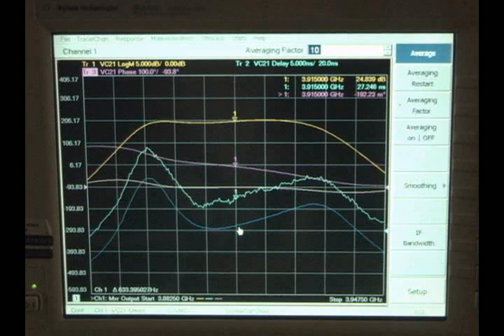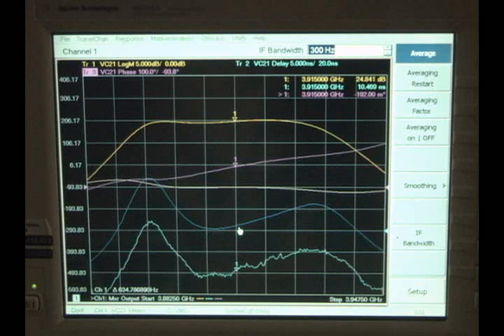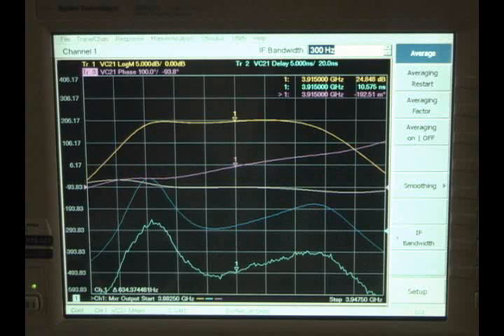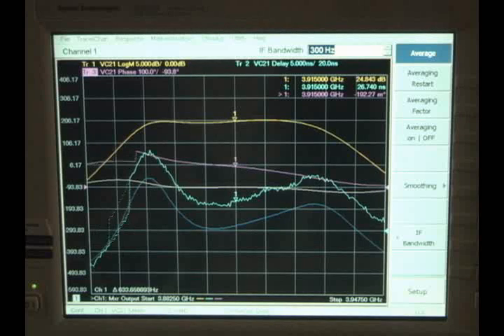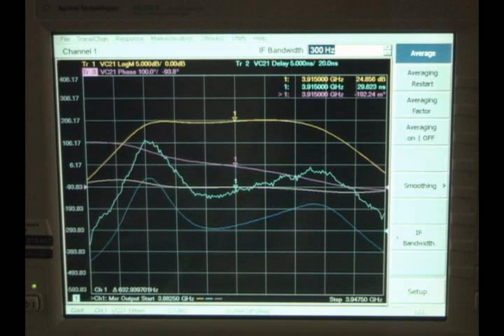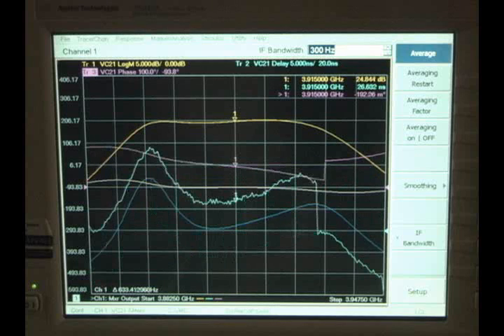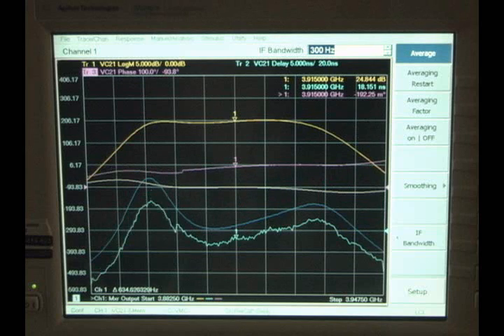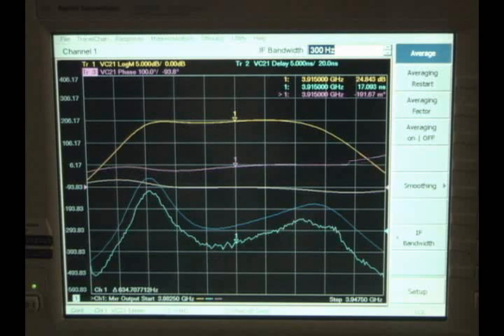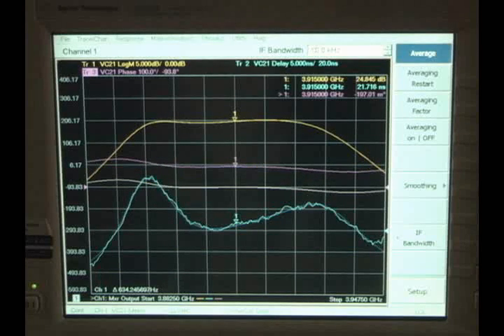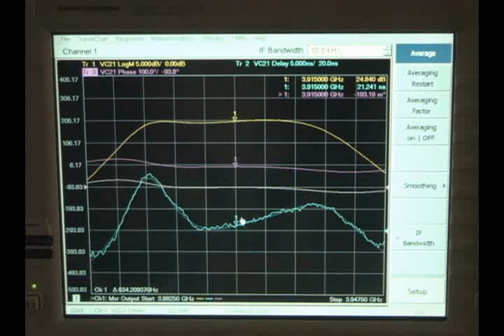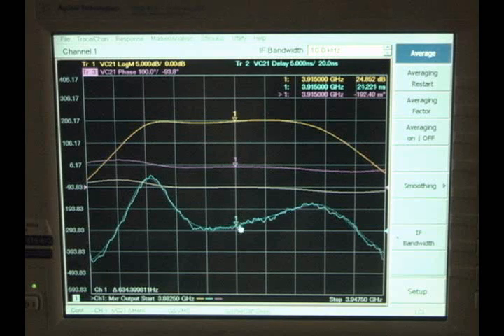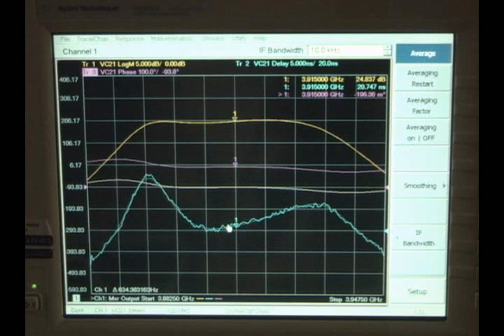That problem is due to the IF bandwidth. When everything is phase synchronous, you want a narrow IF bandwidth to get good noise performance, to minimize the trace noise. However, in an embedded LO measurement, that narrow IF bandwidth is actually causing the measurement to degrade the group delay measurement because the frequency instability now is moving on either side of the filter skirt or the side bands of the filter. So in order to stabilize the phase and group delay measurement, we need to widen up the IF bandwidth. So I'm going to widen it up to 10 kHz. And you see now that we have much less movement in the group delay trace, and you'll notice now that it's much closer to being centered around the correct value that's shown in dark blue.